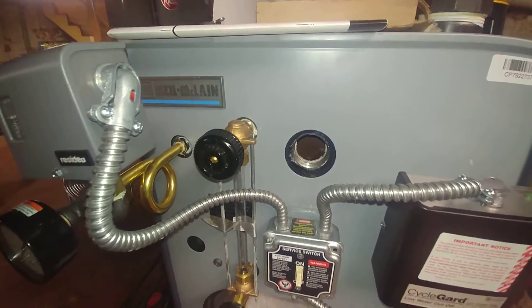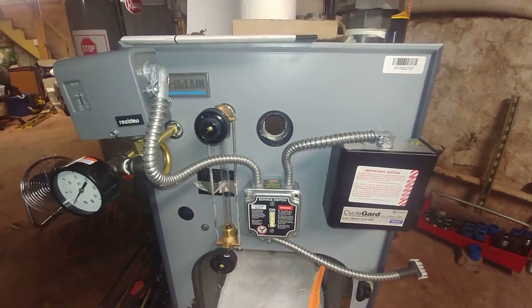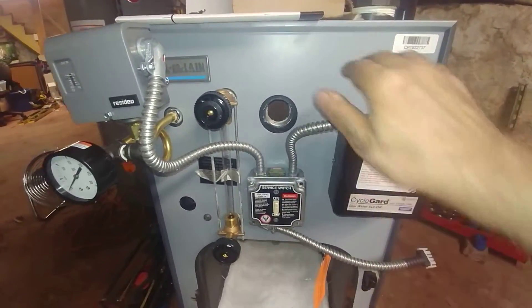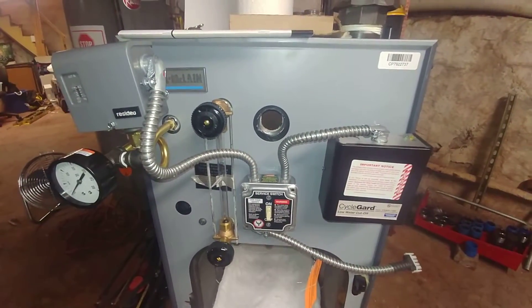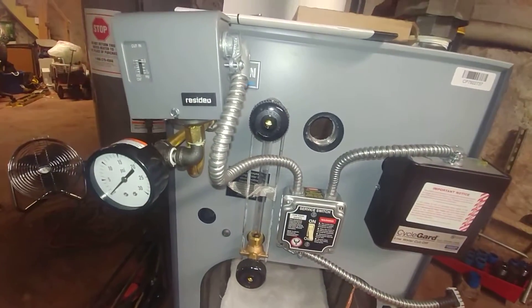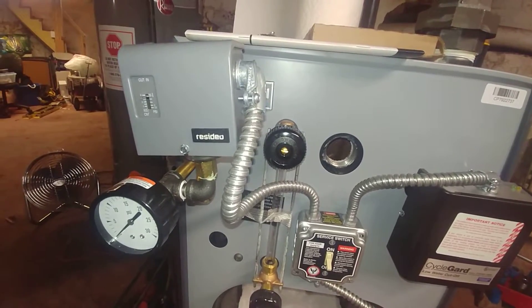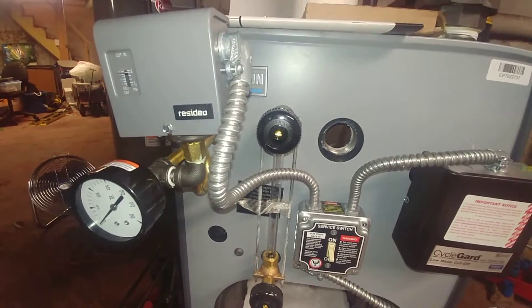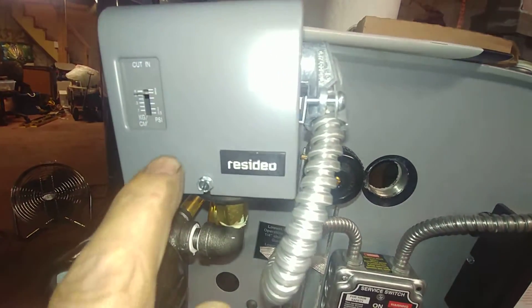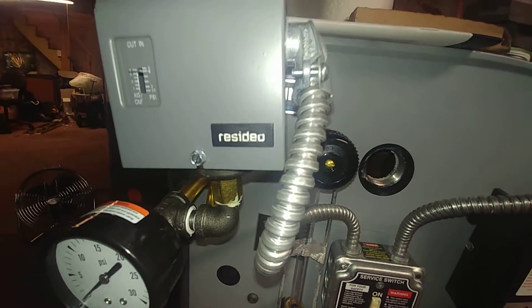It's a Weil-McLain SGO — this is their new color, their new series. Pretty much the same boiler as far as I can tell, just a different color jacket. But what I wanted to discuss is the pressure controller. This is now made by a spinoff from Honeywell called Resideo, and this is the way it comes — they've got that cranked up to 8 PSI.